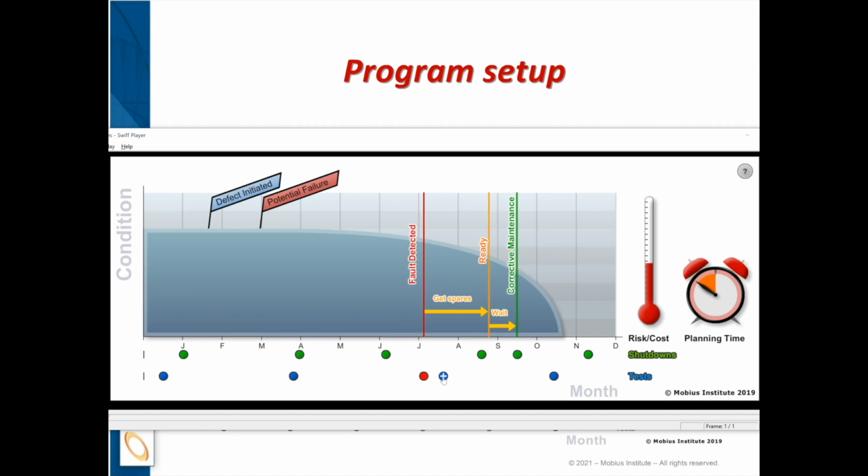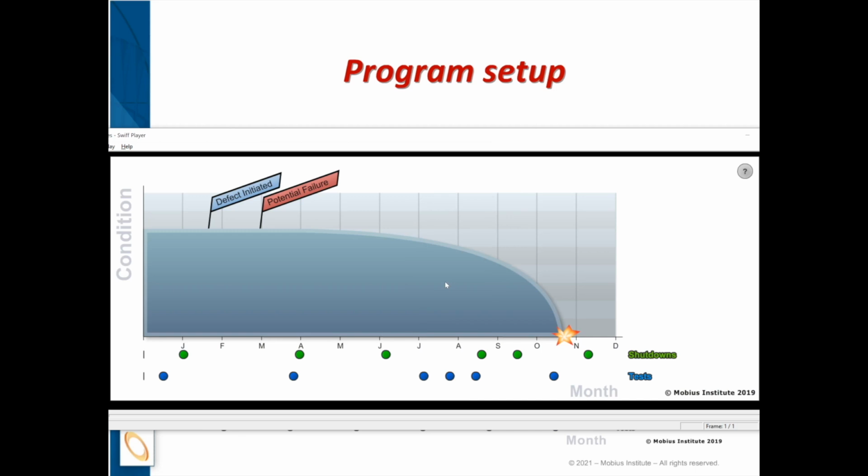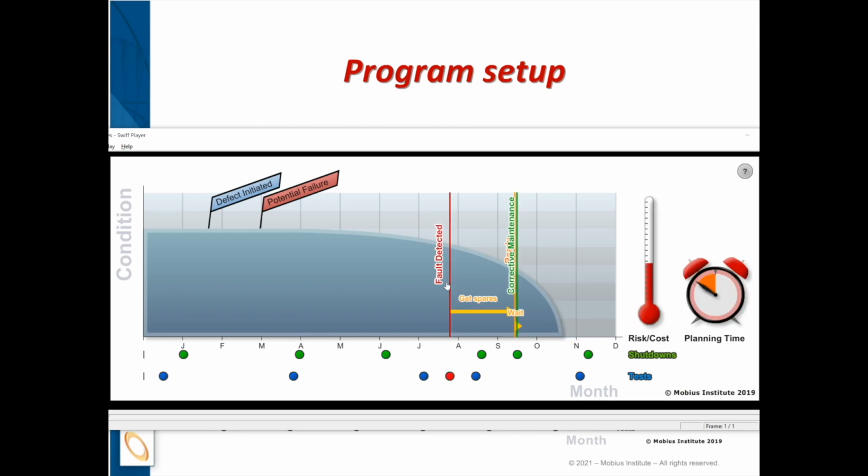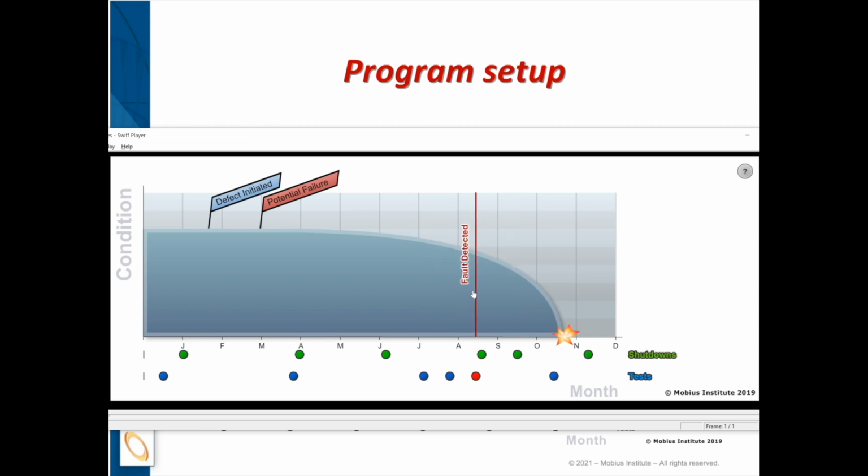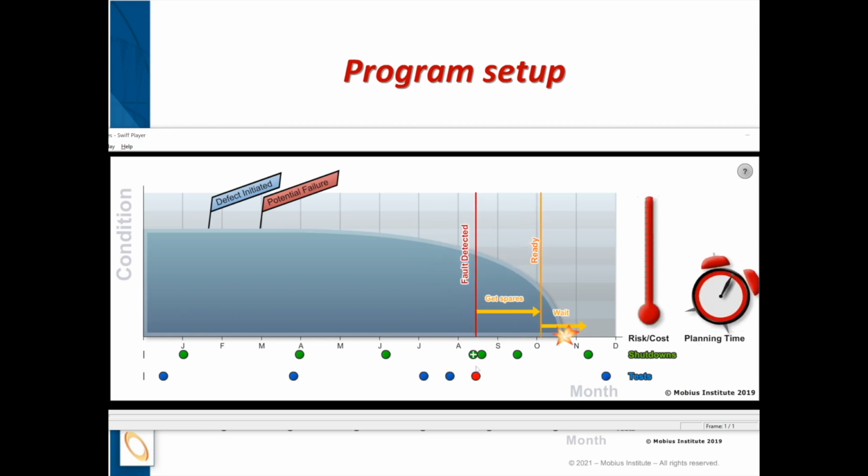what the health is and perform the work, then I could add additional tests and say, well, what was the condition here? Okay, am I comfortable now to make the call that the equipment needs to be taken out of service? Or do I wait until this measurement interval? Again, because we are performing additional measurements to find out what's going on. And here, oops, we missed it, so we need another shutdown. So you see there's this relationship between the two things.